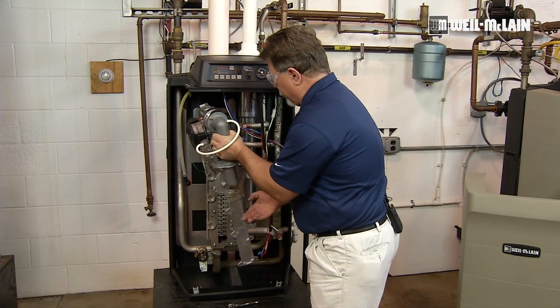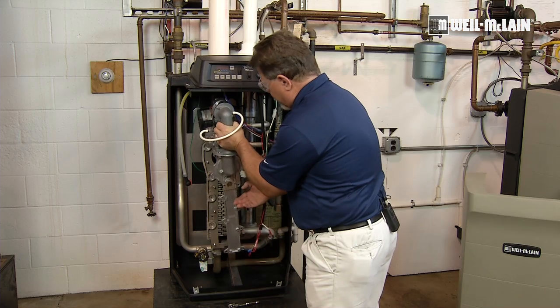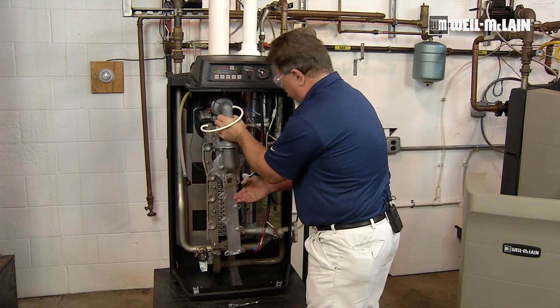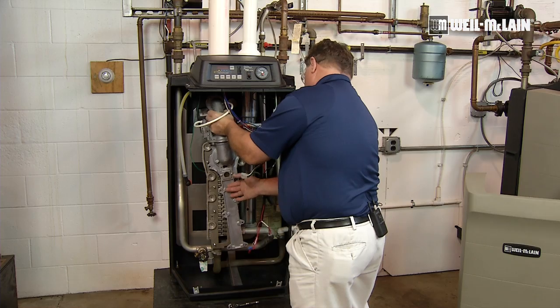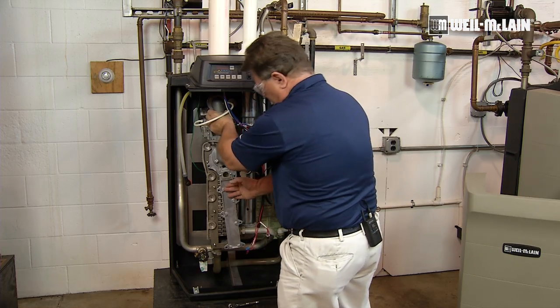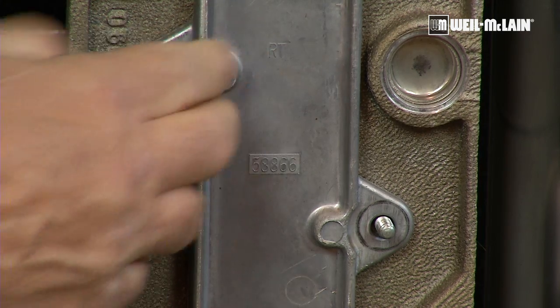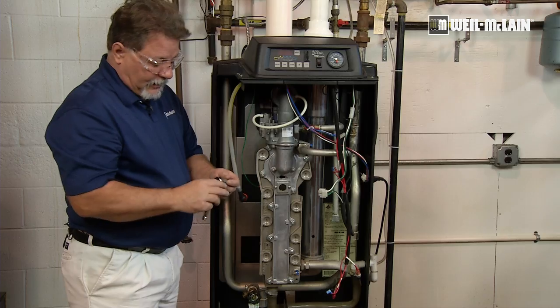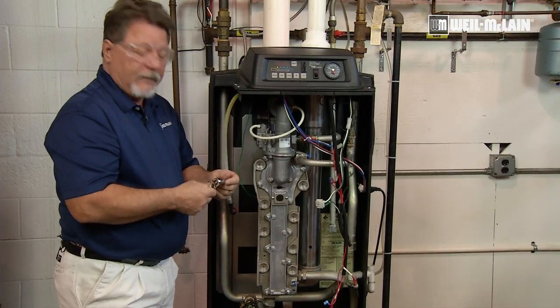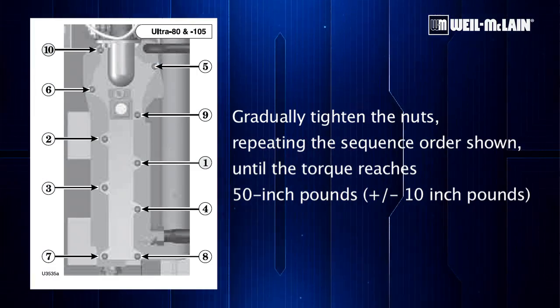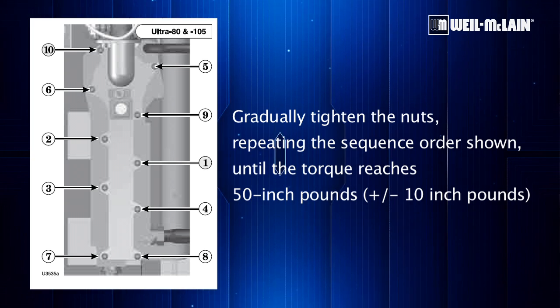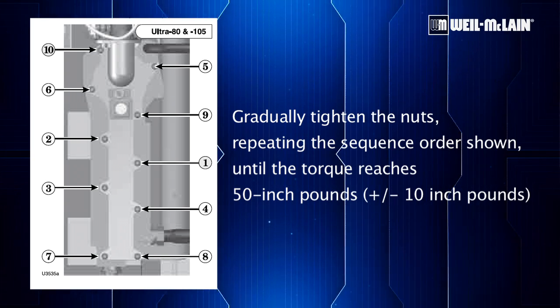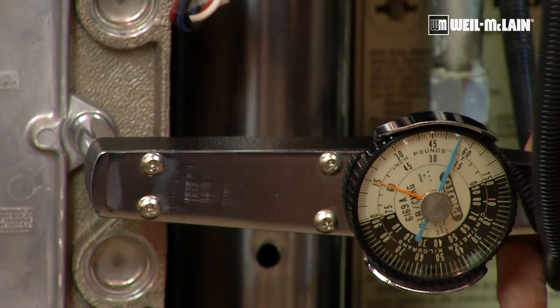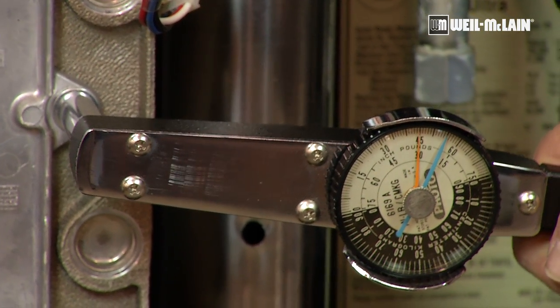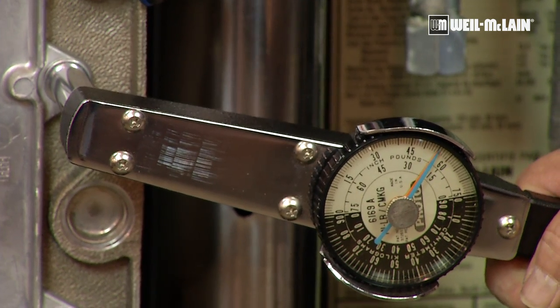We want to insert the burner into the combustion chamber and set the cover plate on the pins. Now after I have all the nuts mounted finger tight, I'm going to take my socket wrench and just snug them up. Later on, we're going to be using a torque wrench, and we're going to set these nuts to a torque of between 50 and 60 inch-pounds.